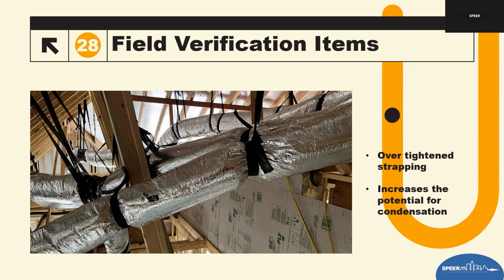If you go through this duct and you look at it, even though it's still insulated, the insulation is crushed. That increases the heat being gained at every single point. So that's just about every 4 feet. But if you look in the far side of that picture, right in the middle, they're using multiple layers of strap in a saddle configuration, not having the problem they see here in the supply. My assumption is the furthest one out is a return, in my opinion far less of an issue than what we see on the supply duct that's right here in front of us.